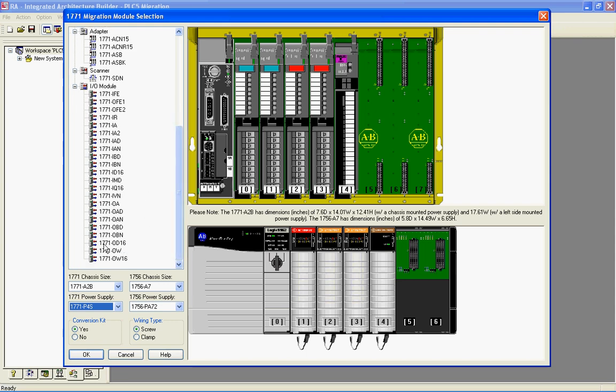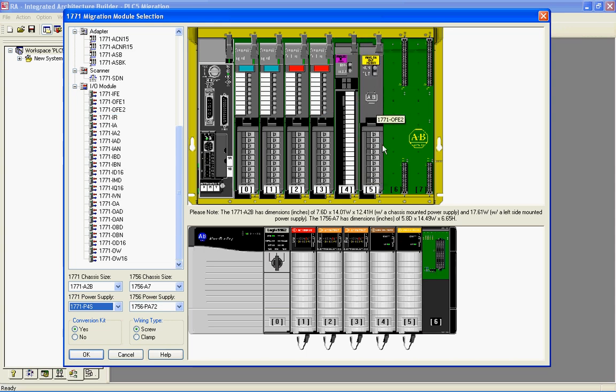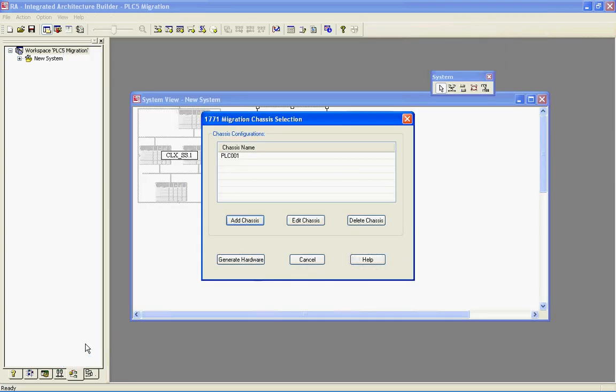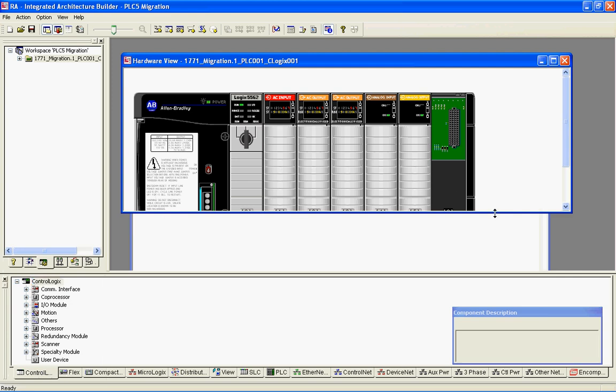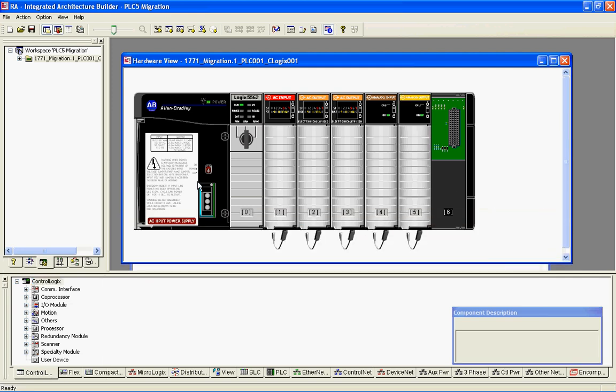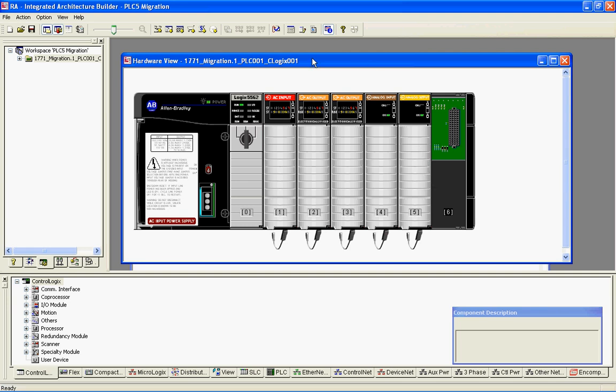I'll pick an analog output module — an OFE — and drop it in the chassis. As I'm doing that, you'll see this ControlLogix image at the bottom, along with the wiring conversion modules, gets placed into the chassis. From here I can select OK and then generate hardware. It pops me back to the system view screen, and if I go to my hardware tab, you'll see it has generated the image of my ControlLogix chassis with the modules and the wiring conversion system.